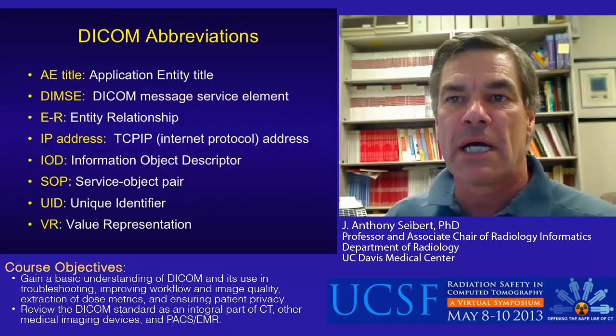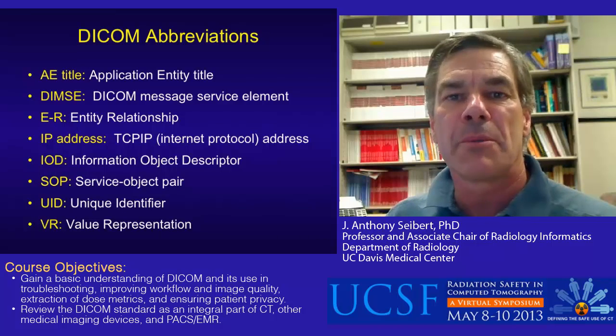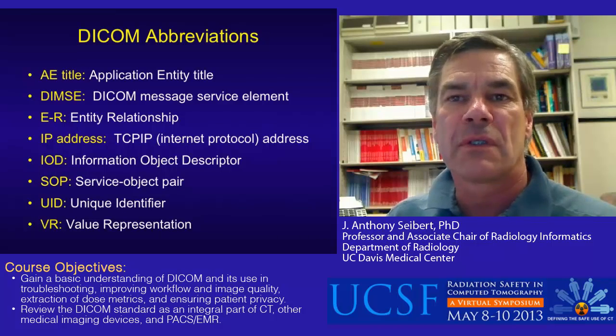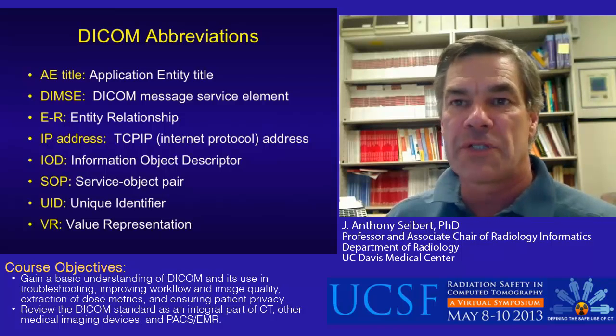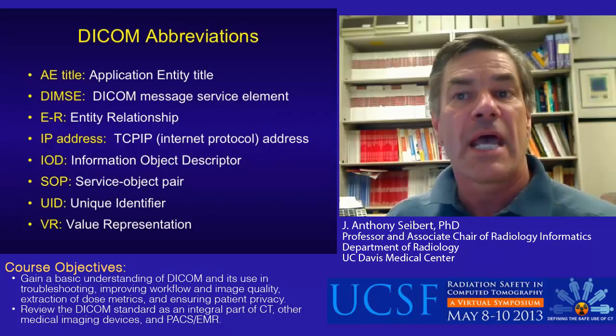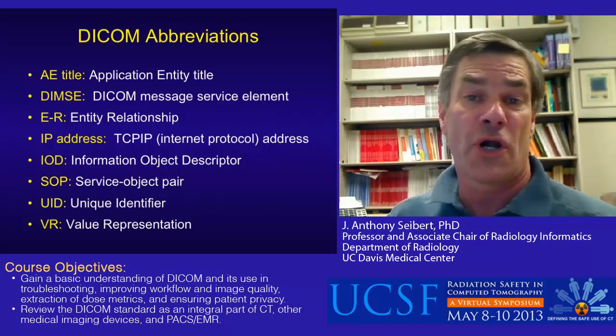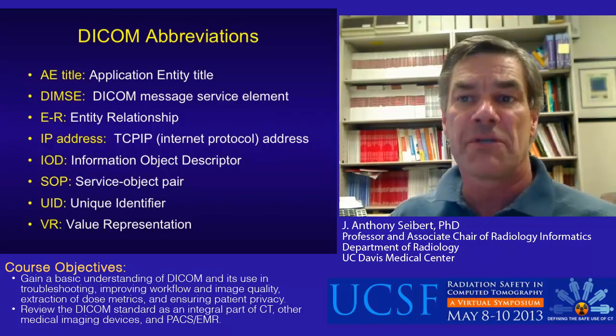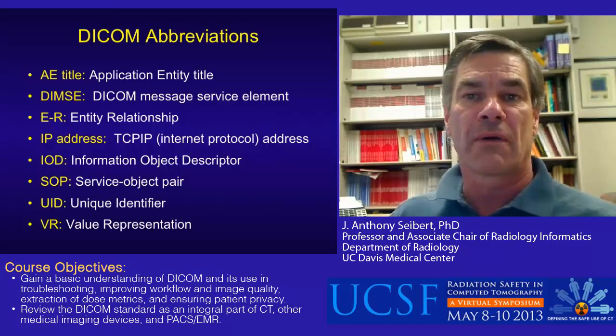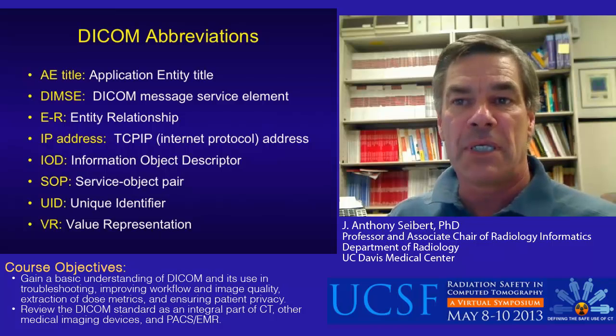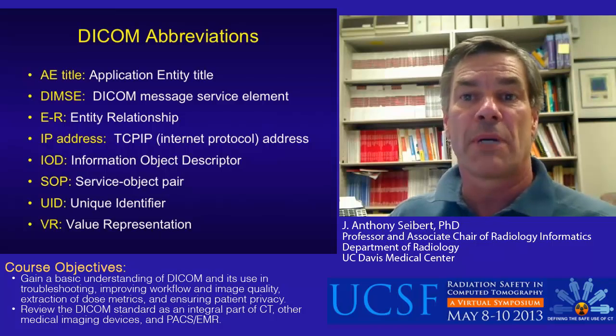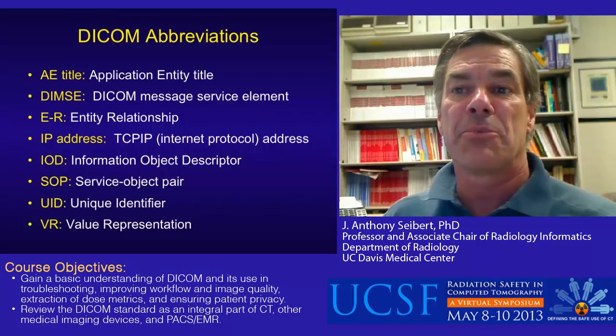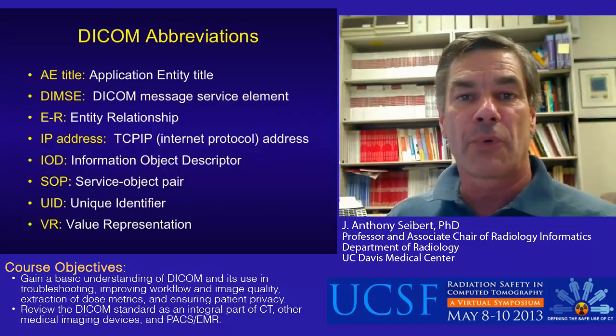When working with DICOM, it is important to understand the acronyms and abbreviations. Listed here are some of the more frequently encountered terms. For example, an AE title — the application entity name, such as cardiac CT — is given to a device which specifically identifies it within a network. Together with the unique IP, internet protocol address, and port number, the device is recognized and is able to communicate on the network using DICOM protocols.